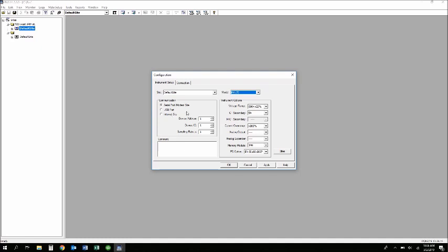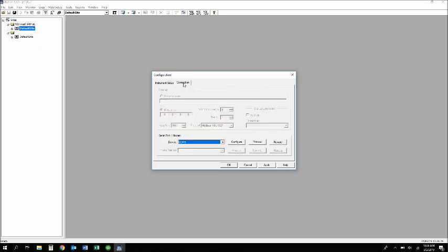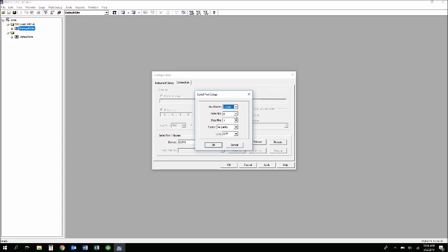The first thing you would want to do if this is a new meter, you would want to use the default setup. The default setup is already predefined in this meter here, and you'll find a COM5, which would be a USB to serial converter because we're doing serial communication. The default is always 19200 baud rate, 8 data bits, 1 stop bit, parity none, and DTR off. And we always have Modbus protocol, RTU, response timeout, breakout, retries, and transmission delays. You'll never have to change these, but if you want, they're there.